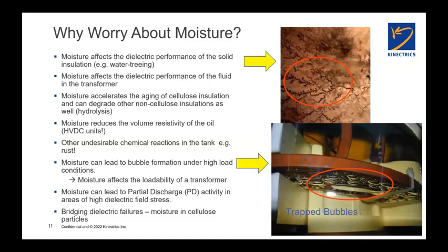They're an area of very low dielectric strength, and you're going to get partial discharge and quite possibly, quite probably, catastrophic dielectric breakdown. In the picture on the bottom right here, we see a disc winding, and we can see some streamer bubbles coming from that, and also some trapped very large air bubbles below the disc. So it's a very real effect. And transformers that have a lot of moisture in the insulation structure cannot be loaded, or should not be loaded, in a way that produces these bubbles. So it's a limiting factor.